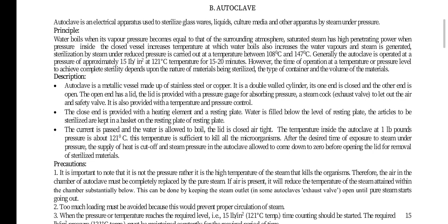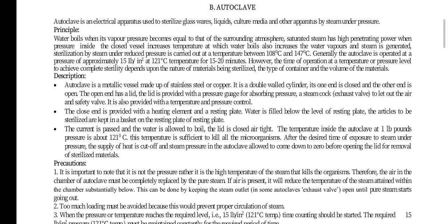Generally, the autoclave is operated at a pressure of approximately 15 lb per inch square at 121 degrees temperature for 15 to 20 minutes. The time of operation at the temperature or pressure level to achieve complete sterility depends upon the nature of materials being sterilized, the type of container and the volume of the materials.